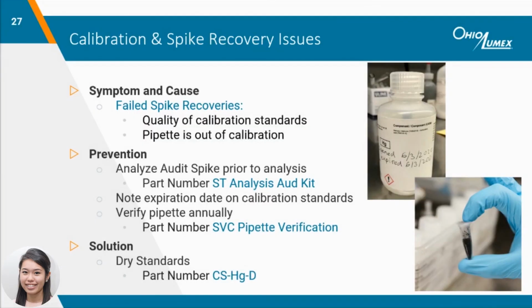A bias can also occur from using expired standards or using a pipette that is out of calibration. It's good laboratory practice to note the expiration date of each standard to ensure standards are still valid. An audit spike will always be helpful to independently verify your calibration. We also recommend verifying your pipette on an annual basis to make sure pipette volumes are accurate.